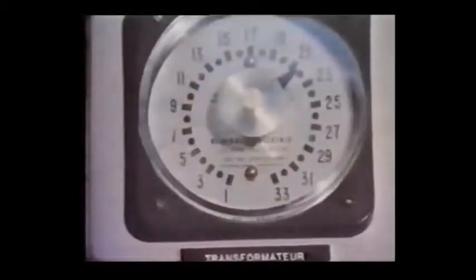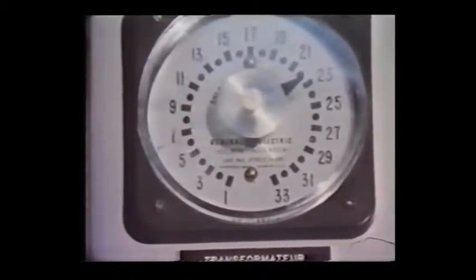Inside the valve hall, this advanced system of interconnection is specially designed and fabricated so that electrical stresses are kept at a safe level. So important is this feature that special care was taken to eliminate any sharp projections on all of the equipment, even a projection as tiny as 1 millimeter that could result in electrical discharge. The system operates at 500 kilovolts, with overvoltage surges up to 1175 kilovolts.